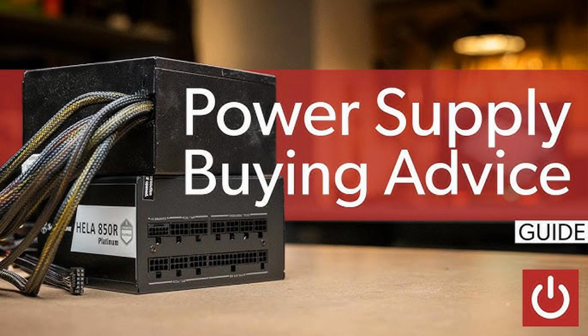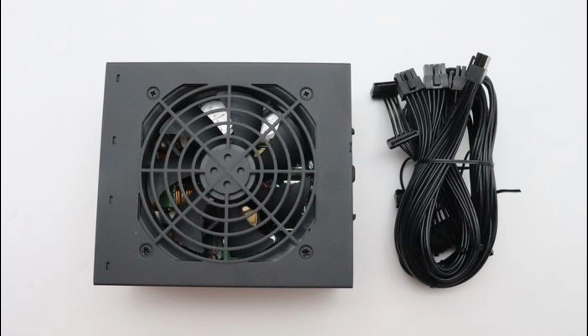7. Compliance with safety standards. Isolated power supplies are often required in applications subject to strict safety and regulatory standards: medical devices must meet IEC 60601 standards for patient safety, industrial control systems require isolation for robust performance and safety, and telecommunication equipment adheres to industry standards for noise immunity and safety.